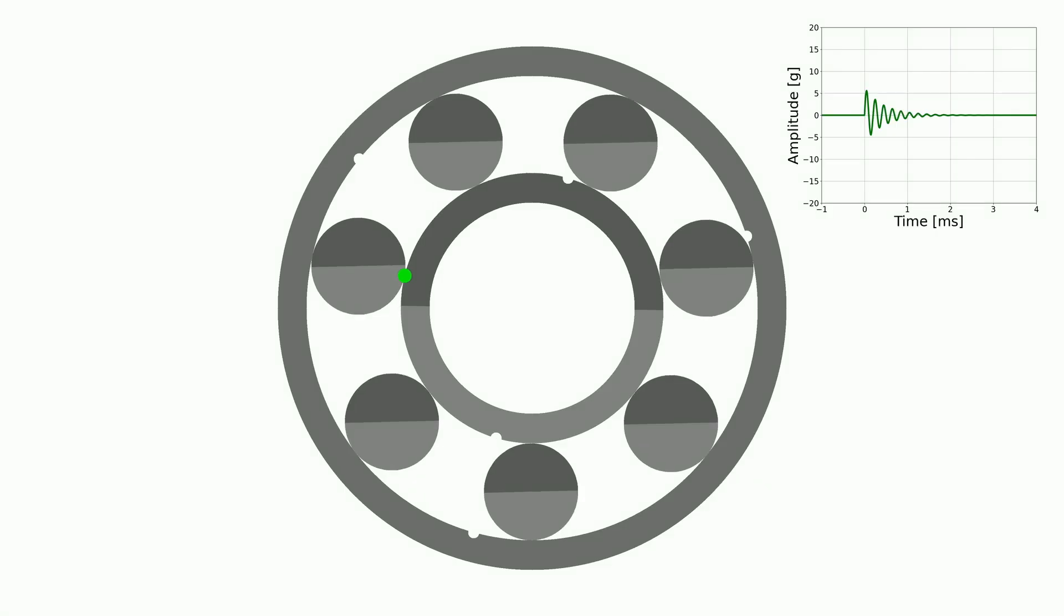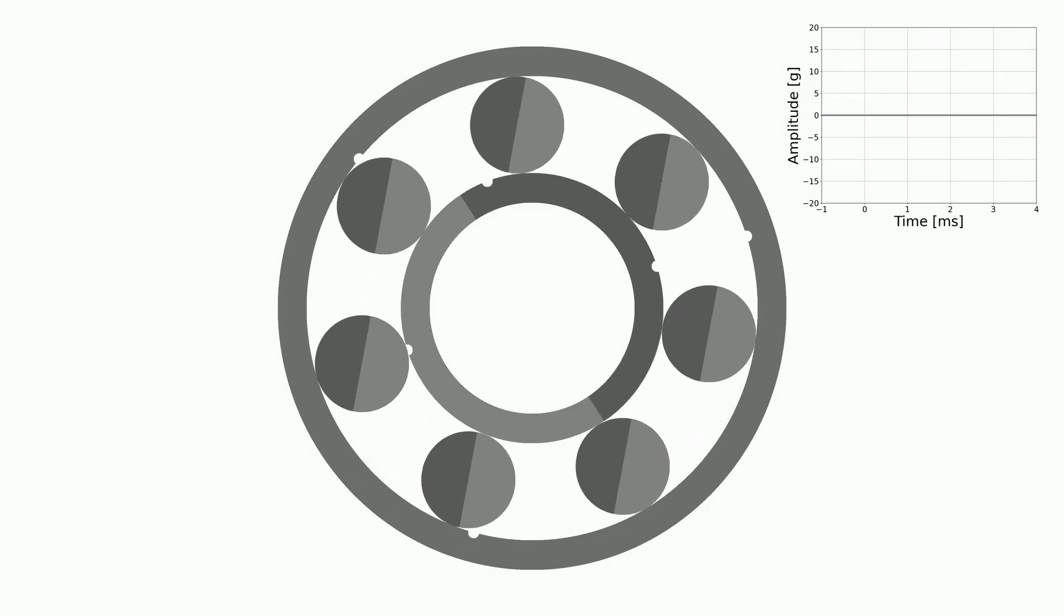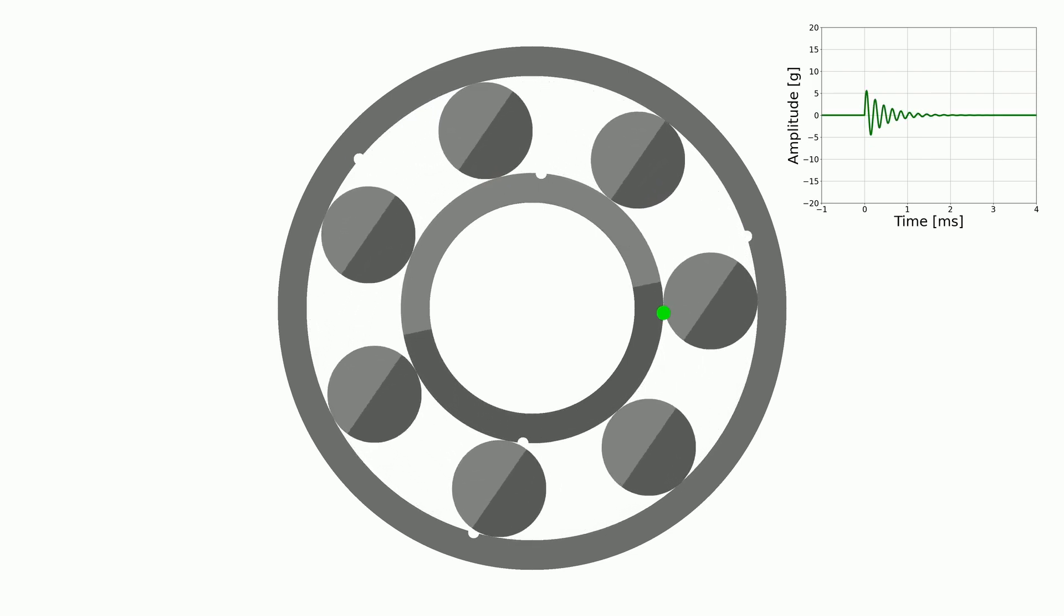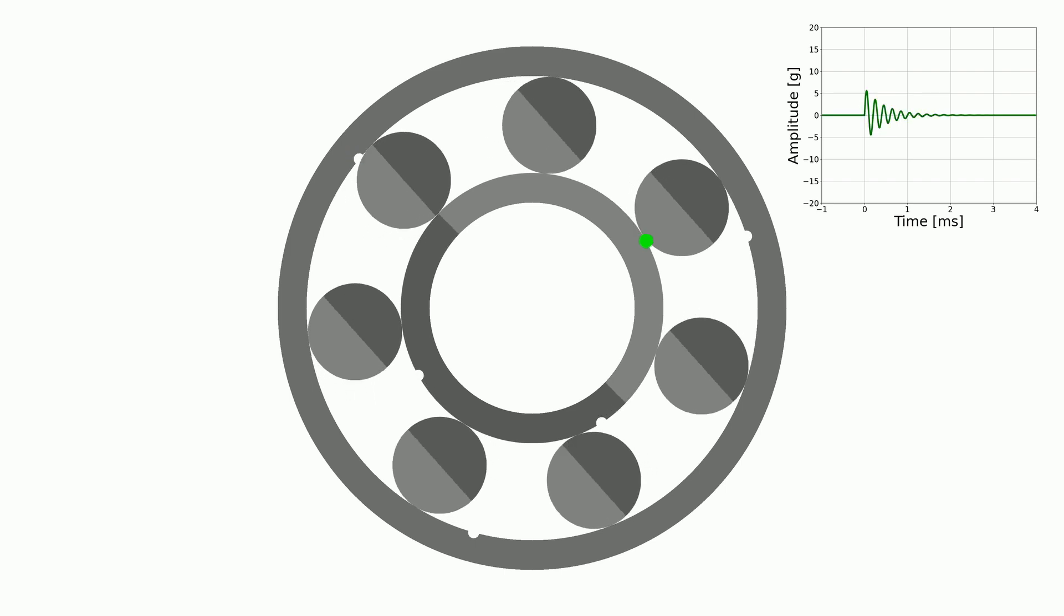Amplitude modulation is very common in vibration diagnostics. For example, it often happens to bearing fault frequencies. Let's examine a ball bearing with seven balls. The inner race rotates at the speed frequency of 25 Hertz.